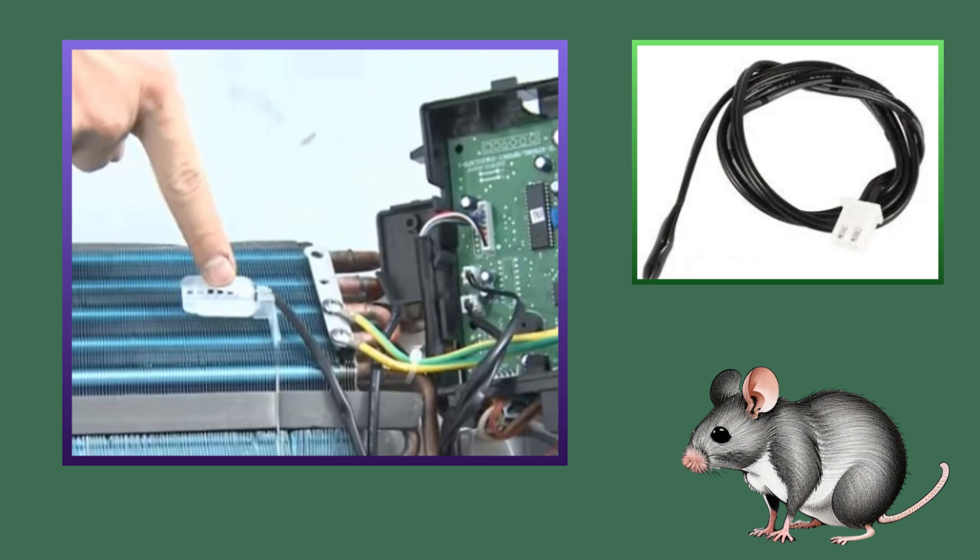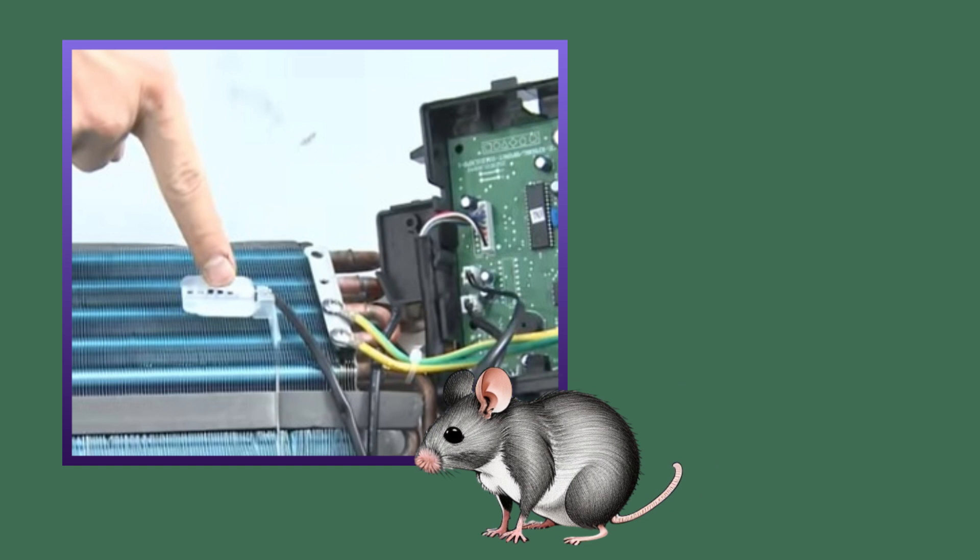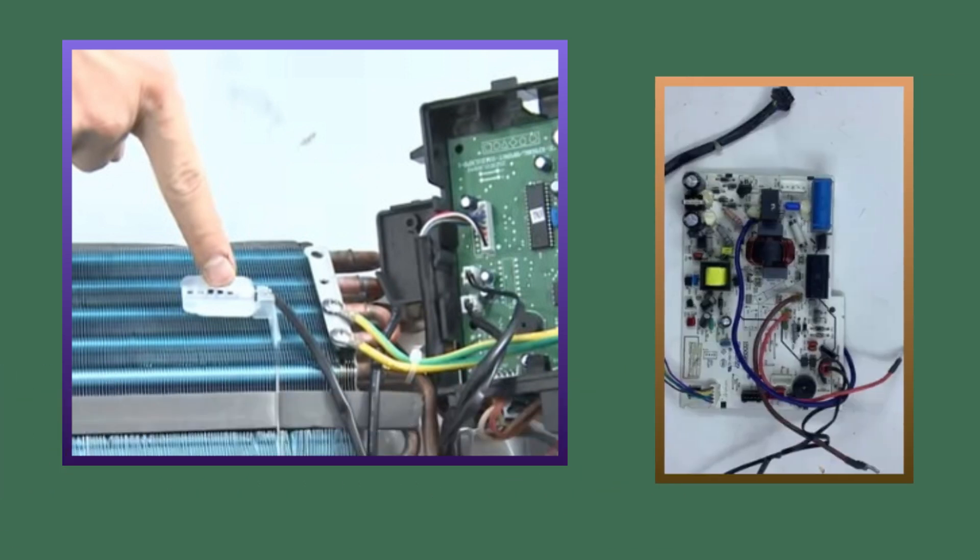And if the rat has not cut the wire of the room temperature sensor and still this error is coming, then you look at the sensor connector in the PCB. This error also occurs due to loose connection.